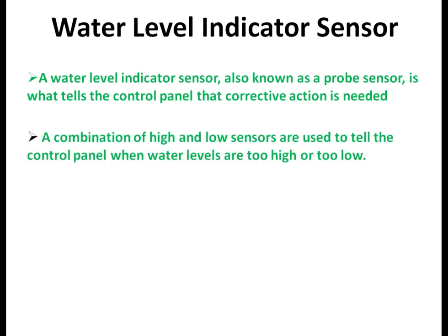A combination of high and low sensors are used to tell the control panel when water levels are too high or too low. In a terminal box we design 2 types of indication, low indication and high indication. When it's low, it gives one signal; when it's high, it gives another signal. So you can keep 2 lamps, one red and one yellow, or you can keep an alarm. When low indication is there, my first alarm will be on. When high indication is there, my second alarm is on. So this is the level indicator.